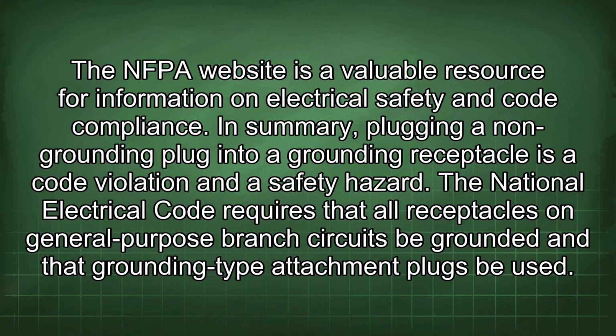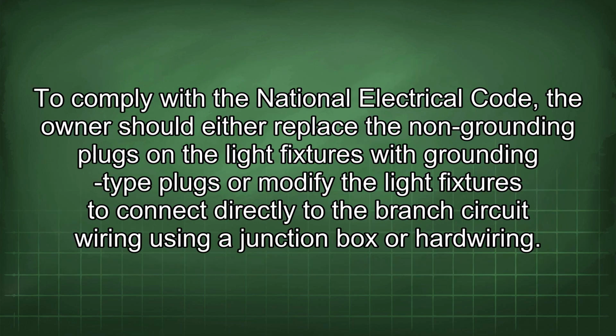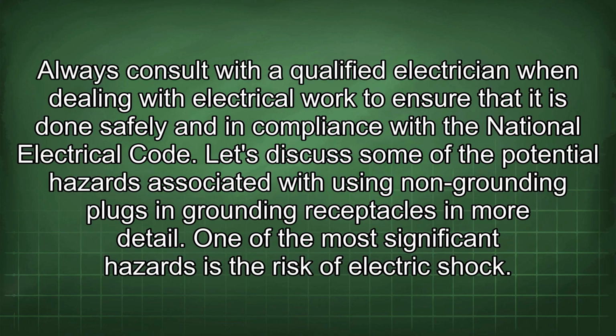In summary, plugging a non-grounding plug into a grounding receptacle is a code violation and a safety hazard. The National Electrical Code requires that all receptacles on general-purpose branch circuits be grounded and that grounding type attachment plugs be used. To comply with the National Electrical Code, the owner should either replace the non-grounding plugs on the light fixtures with grounding type plugs or modify the light fixtures to connect directly to the branch circuit wiring using a junction box or hardwiring. Always consult with a qualified electrician when dealing with electrical work to ensure that it is done safely and in compliance with the National Electrical Code.